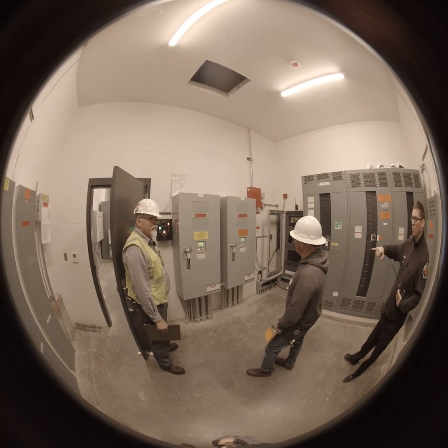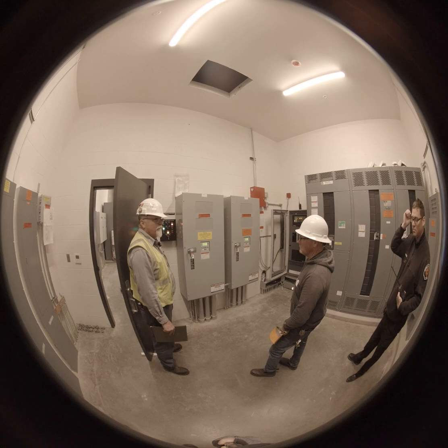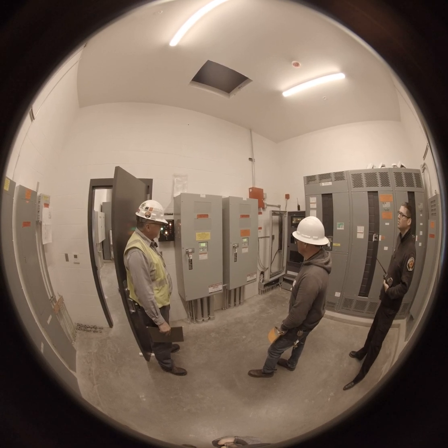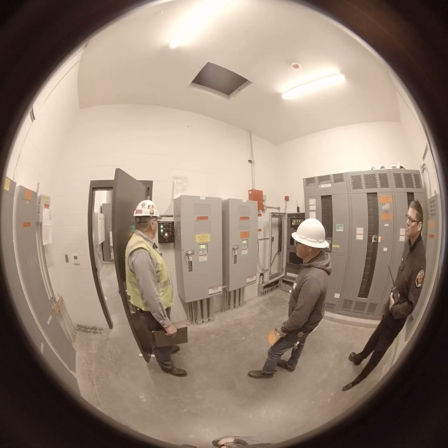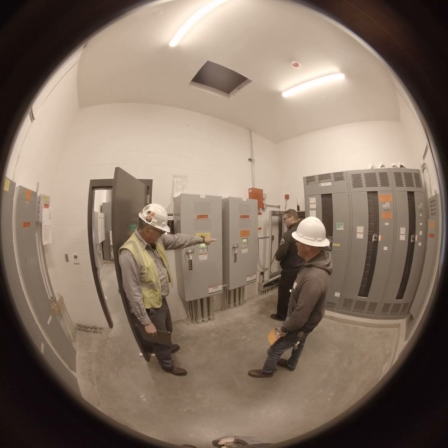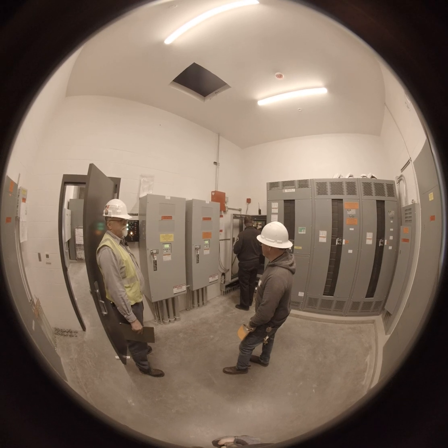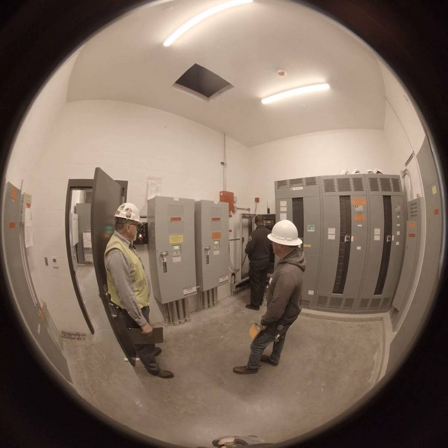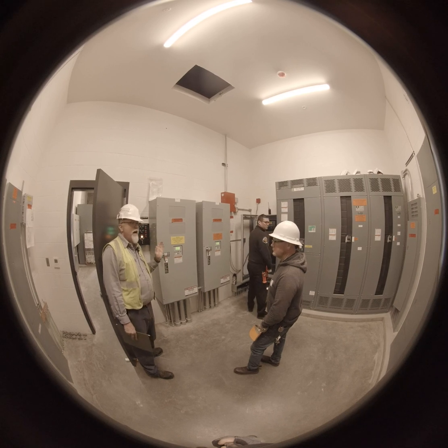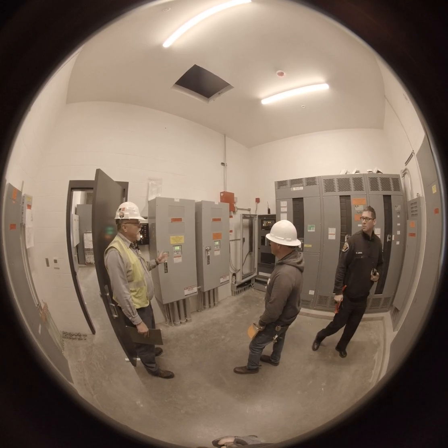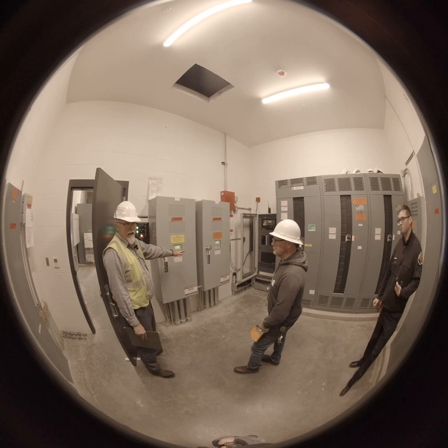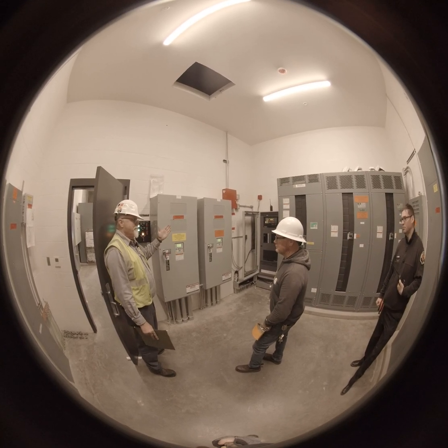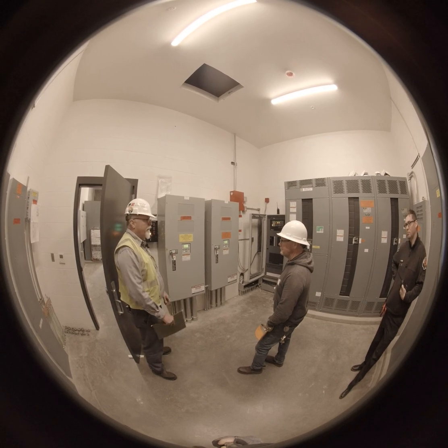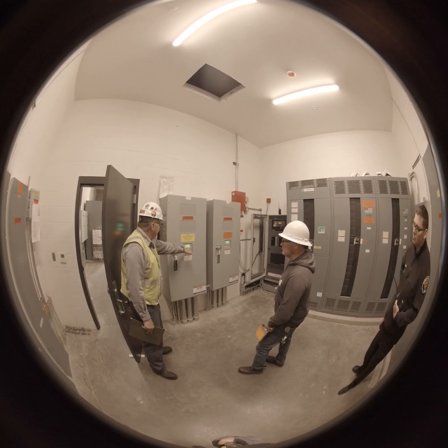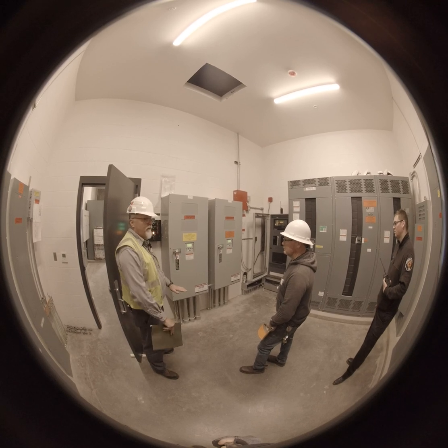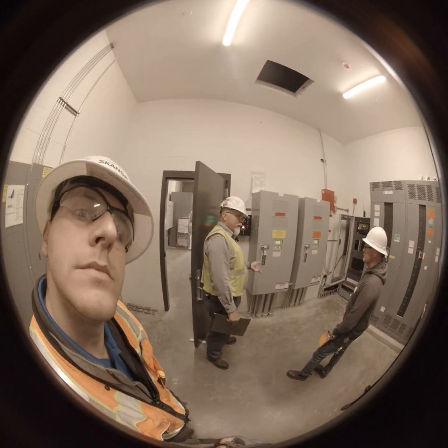So this is emergency power, right? Not standby power, and that's the standby power? Yep. And you're back. Now, you'll see over here, it's got a 5-minute cooldown. The 5-minute cooldown, you cannot bypass. They don't let you. The retransfer, say if you had an actual outage on these here, and I believe I left these set for 5 minutes, and you didn't want to wait for 5 minutes, you can. It'll come up and say bypass, and you push it, and it will basically cancel out that retransfer delay, and it'll go back immediately.